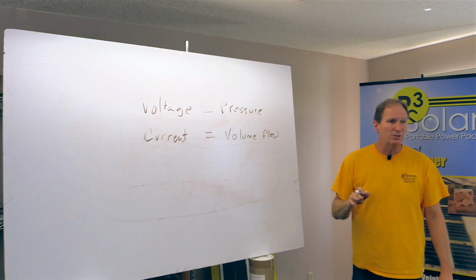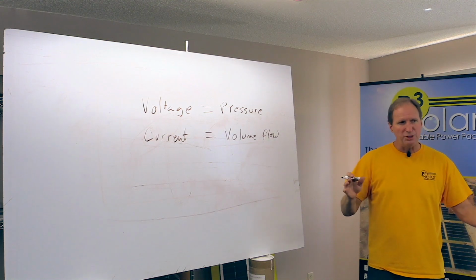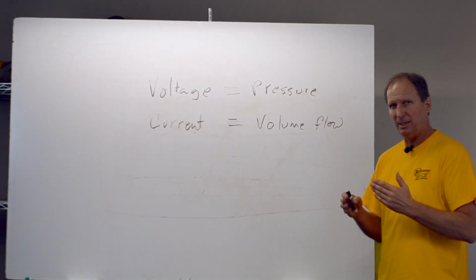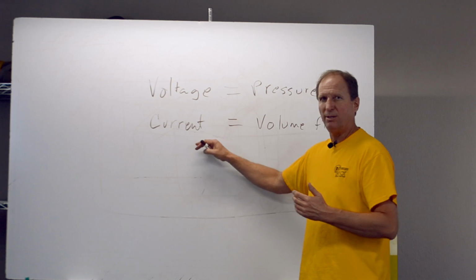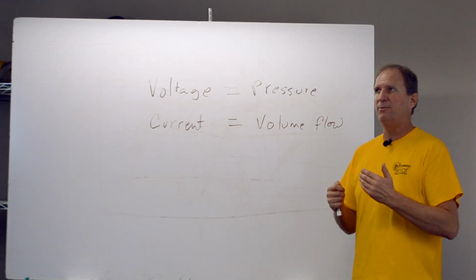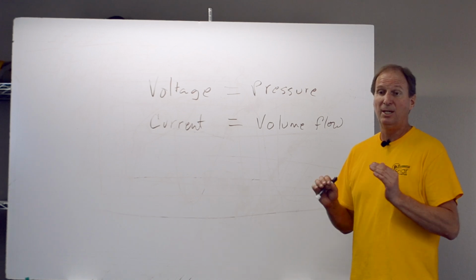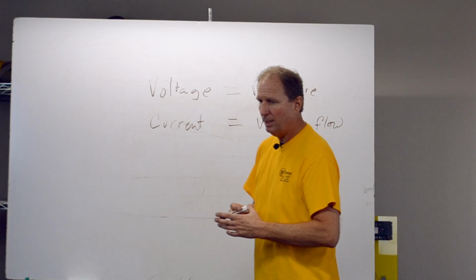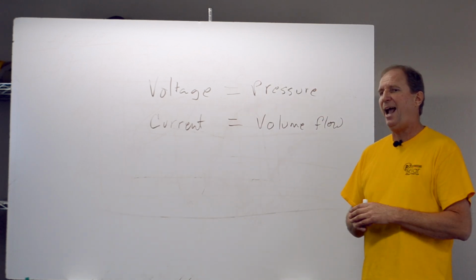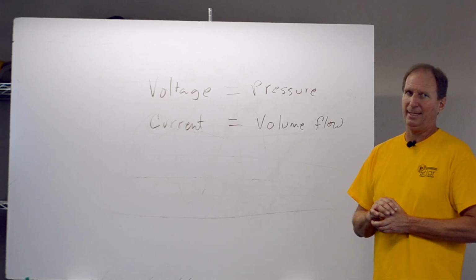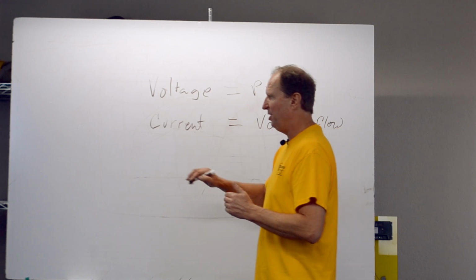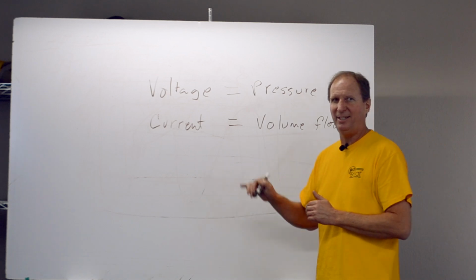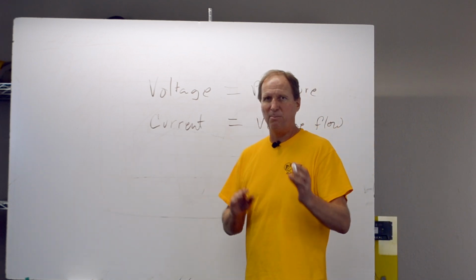So don't worry too much about a power number when you're looking at wire sizes. Typically you're looking at the current flow through the wire. And so when you look for American wire gauge rating for current flow, those are typically done at the maximum temperature the insulation can get. So never go to the maximum current rating of a wire, because that means you're going to get it hot enough to be at the limit of the insulation, which means the hotter you get, the more resistance there is.